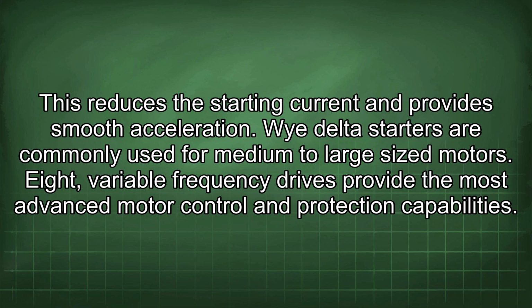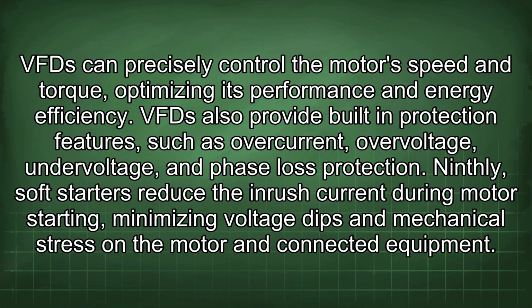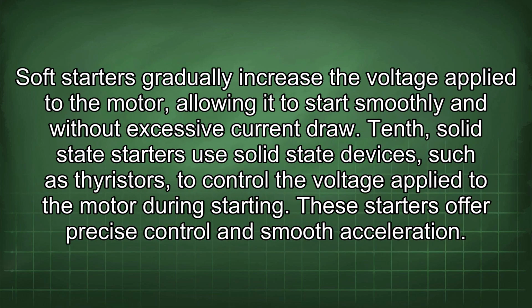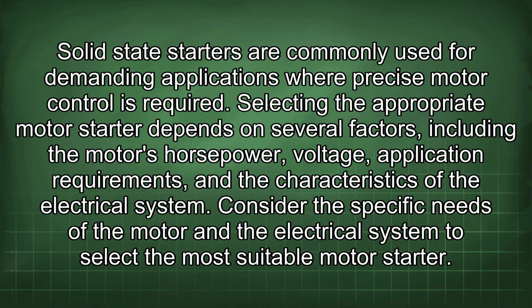Eighth, variable frequency drives provide the most advanced motor control and protection capabilities. VFDs can precisely control the motor's speed and torque, optimizing its performance and energy efficiency. VFDs also provide built-in protection features, such as overcurrent, overvoltage, undervoltage, and phase loss protection. Ninth, soft starters reduce the inrush current during motor starting, minimizing voltage dips and mechanical stress on the motor and connected equipment. Soft starters gradually increase the voltage applied to the motor, allowing it to start smoothly and without excessive current draw. Tenth, solid-state starters use solid-state devices, such as thyristors, to control the voltage applied to the motor during starting. These starters offer precise control and smooth acceleration. Solid-state starters are commonly used for demanding applications where precise motor control is required.